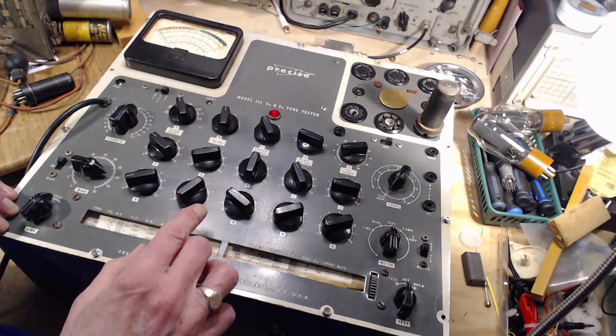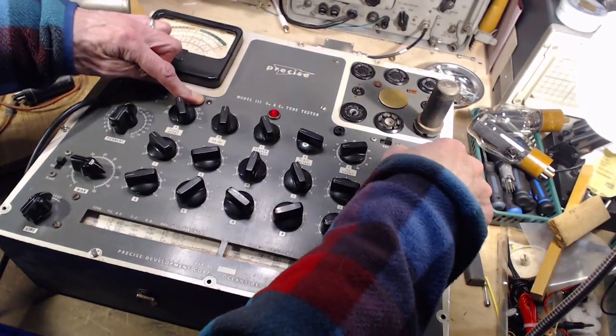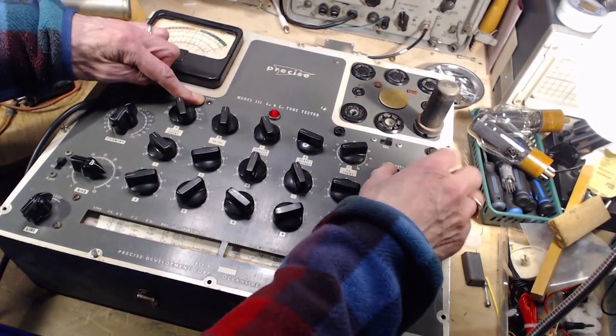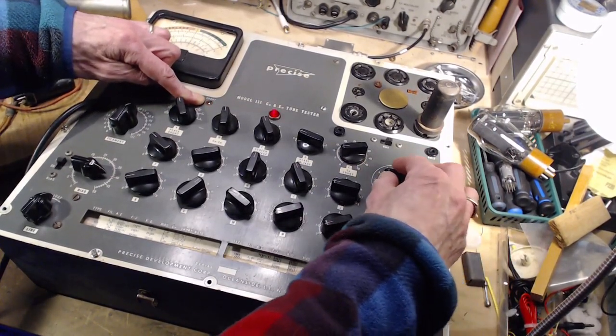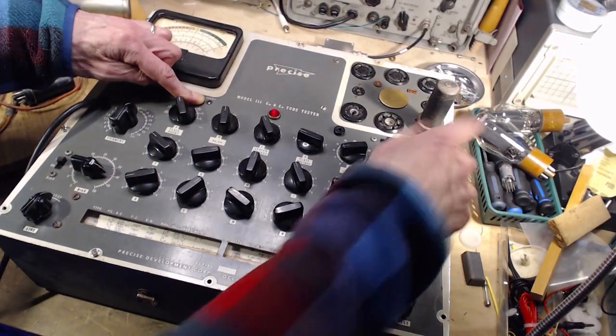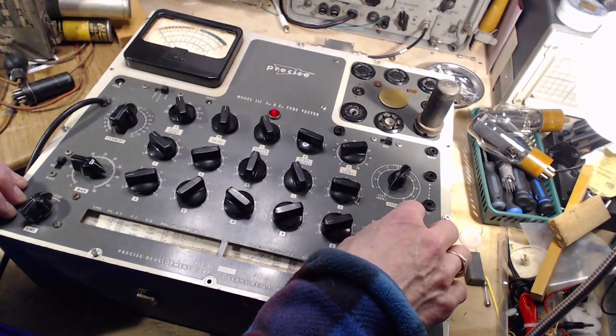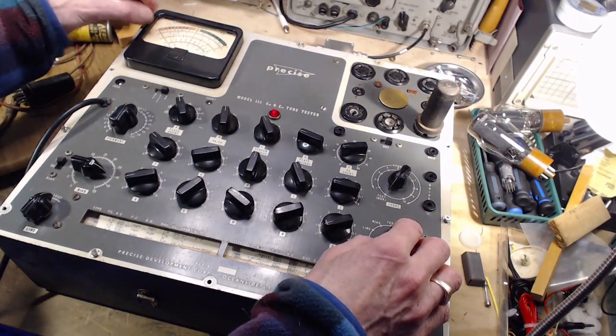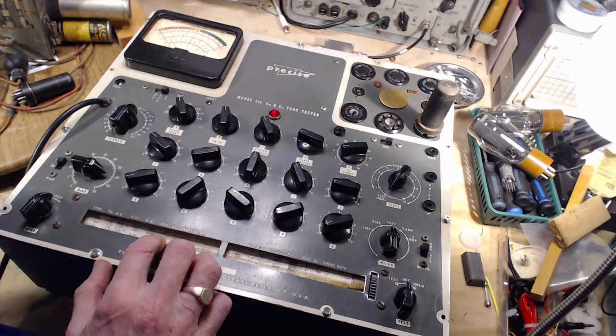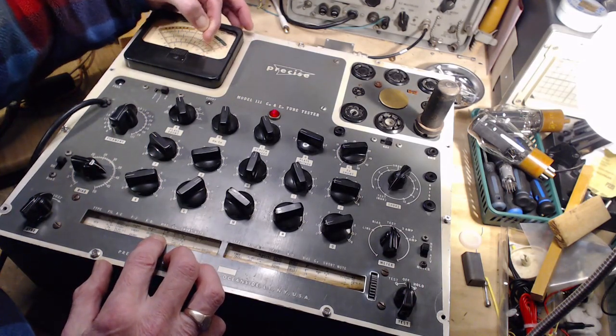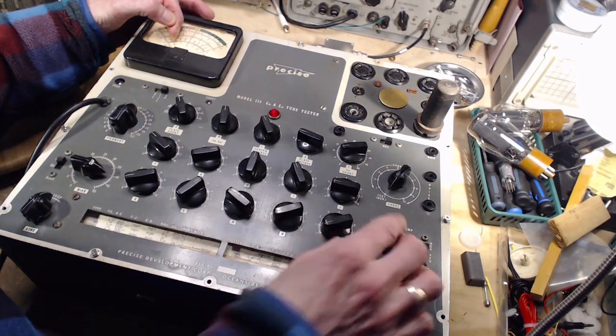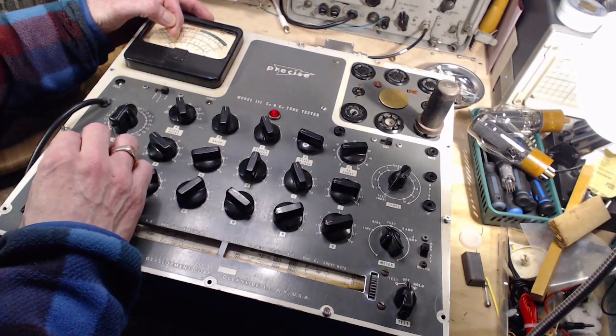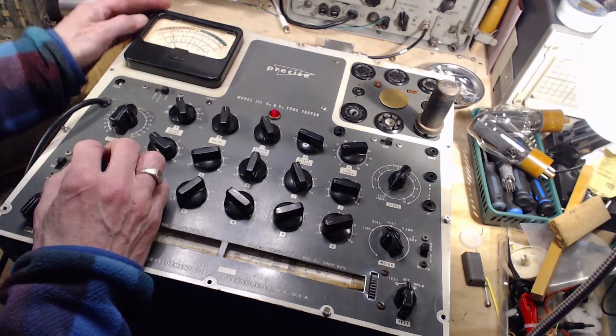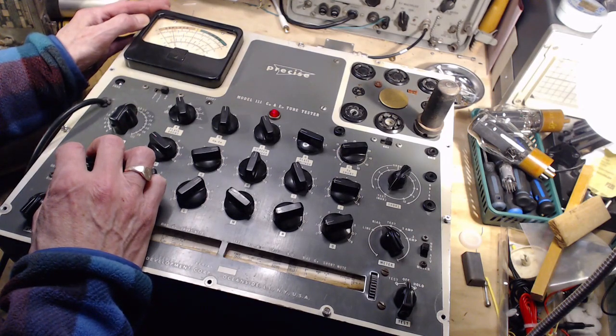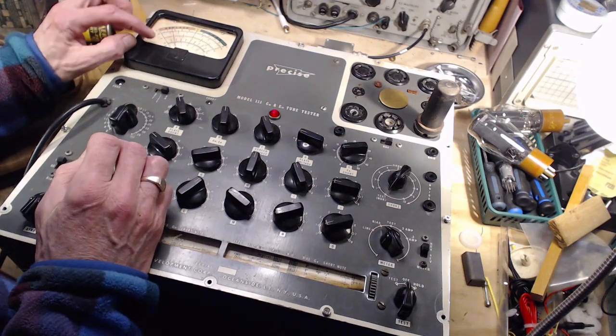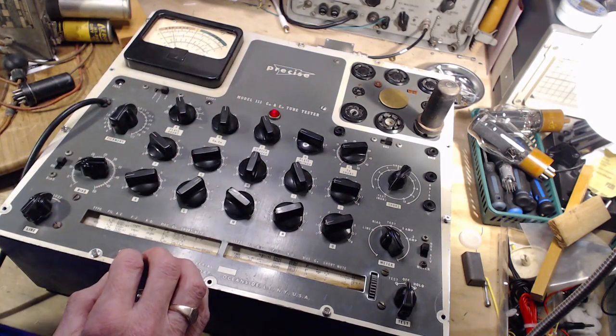Okay, we're ready to do the shorts test. We should see the light come on 2 and 7. That's all. 2, 7. Ready for the test. Except now we check the bias on the tube. Should be 1.4. Is that right? Let's just make sure I'm not wrong. 1.7. I was wrong. So on the 10 volt scale, 1.7 is going to be somewhere up like this. Bias, please. More bias. 1.7. 10 scale 1. That's minus 1.7.